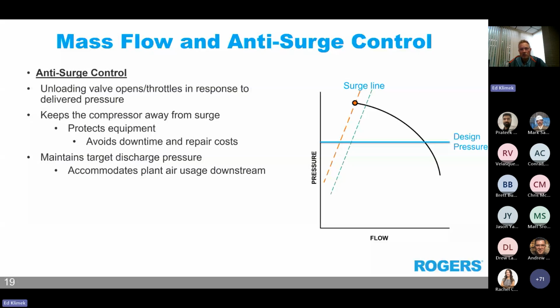The anti-surge control with mass flow works by adjusting the unloading control valve in response to the recorded pressure being delivered to the plant. The primary focus of anti-surge control is to maintain safe operation of the compressor by avoiding surging of the compressor, building excess back pressure at the compressor discharge to the point where there is a reversal of flow through the machine, and thus a potential for equipment damage. So I'll animate a little bit of mass flow and anti-surge control.